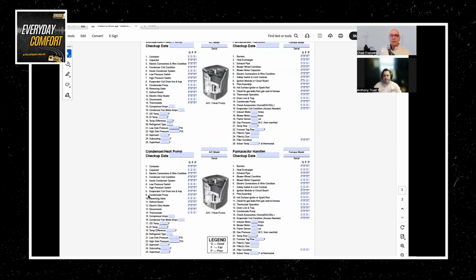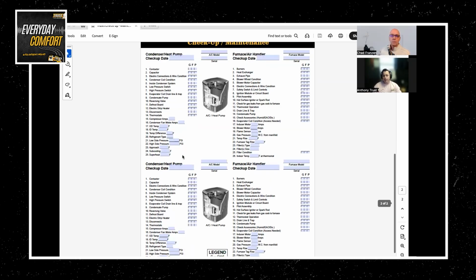Is that really one of the quickest ways to spot a hidden issue? That would probably be the second one. The first one would be hooking up gauges and looking at the pressures. But if your ductwork's not in good condition, or if you have a clogged filter or poor airflow, then your pressures are going to be messed up too. So those things go hand in hand when you're checking pressures and then you're checking airflow.